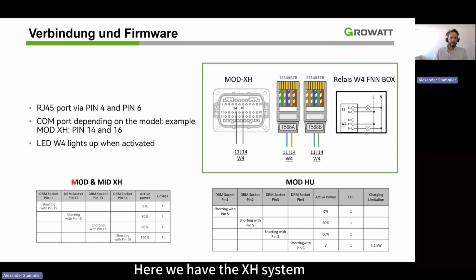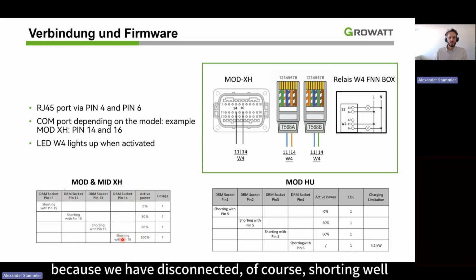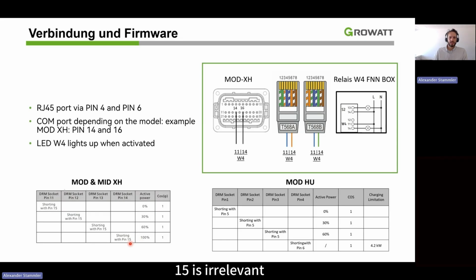Here we have the XH system, so the pins are slightly different because we have this connector, of course. Shorting, well, 15 is irrelevant because 100% is normal. So shorting 13 and 15 means 60% AC output. 12 and 15 is 30% AC output. 11 and 15 is 0% output, so it will stop production totally. And 14 and 16 is the limitation of incoming current for the battery. So that's for the inverter.